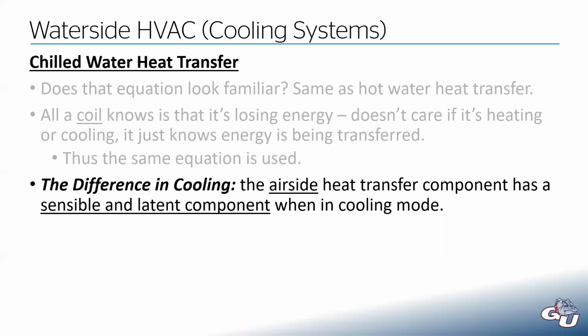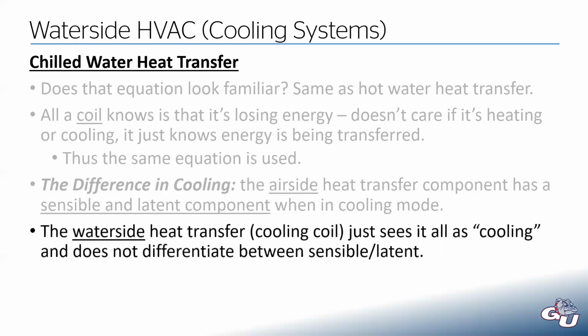And that's not something we see on the heating side. This is unique to cooling. But that's only on the air side of the heat transfer process. The water side, if we're looking at the coil and the fluid that's moving through the coil, that doesn't differentiate between sensible and latent. All it sees is cooling.